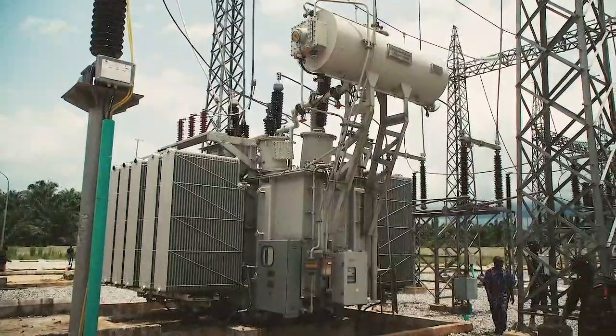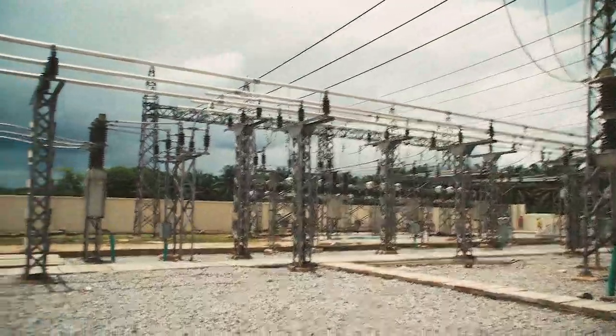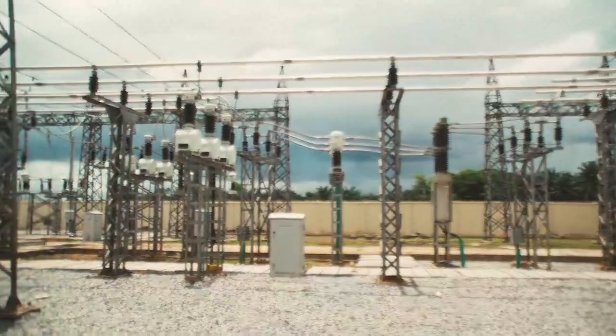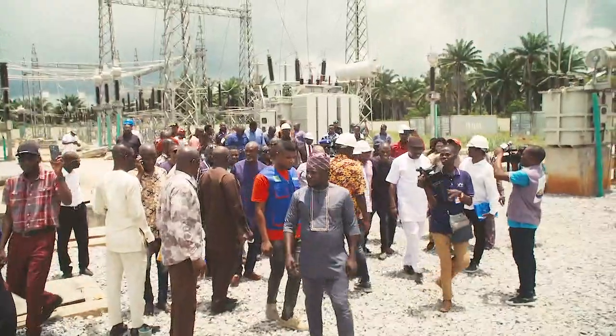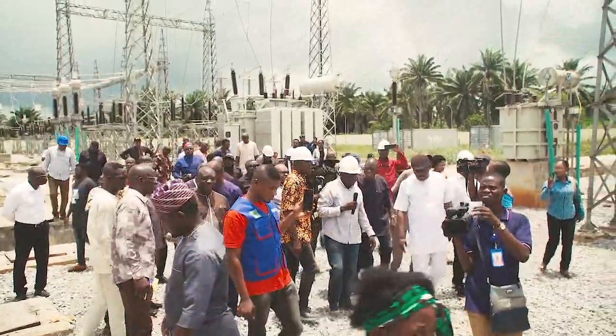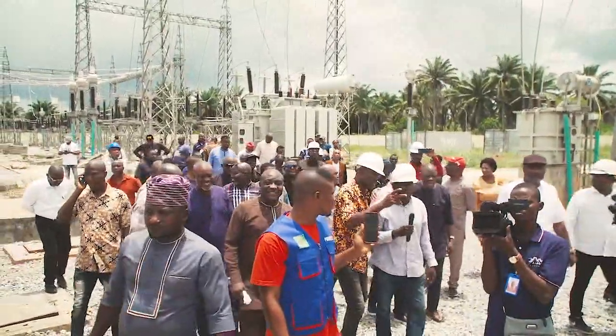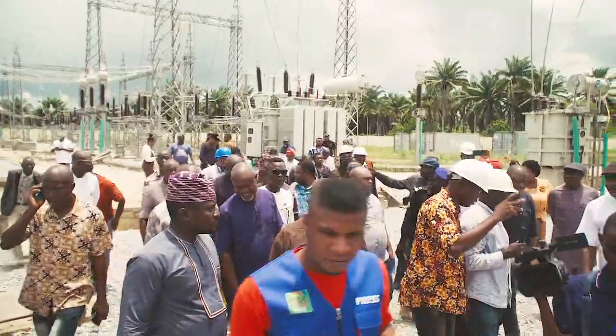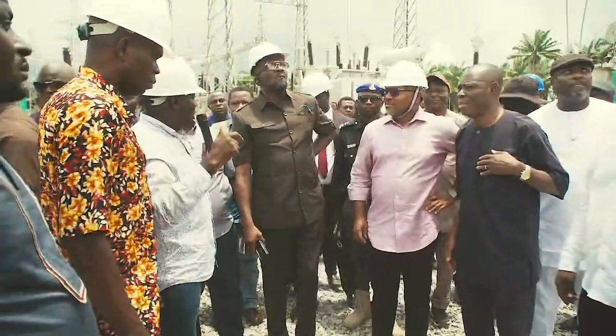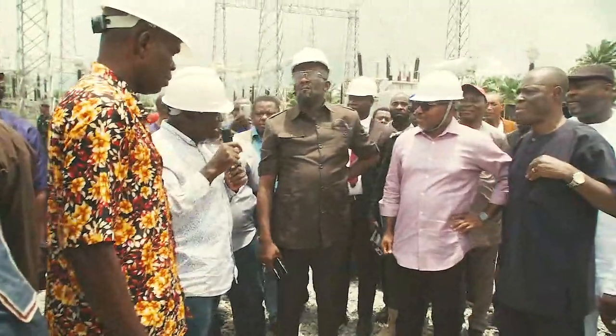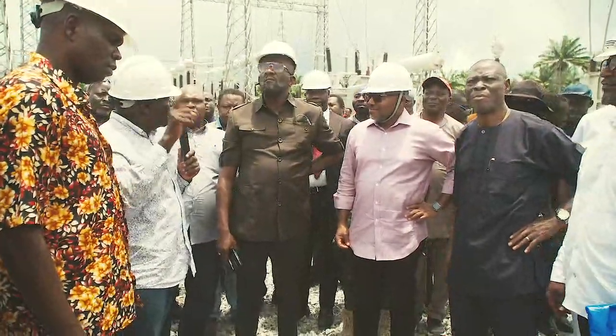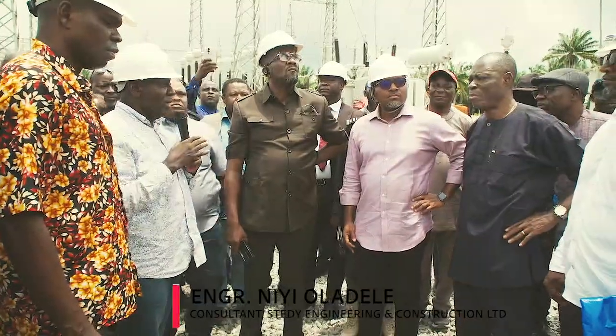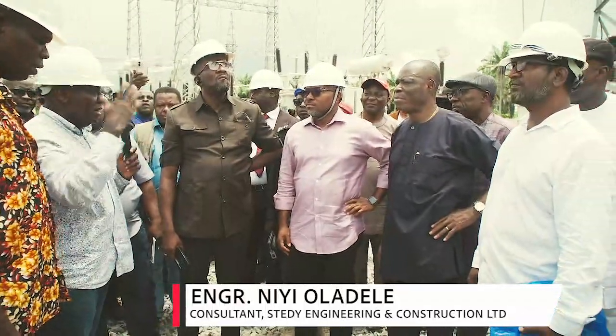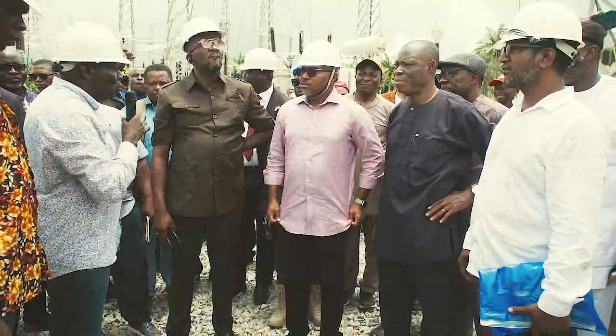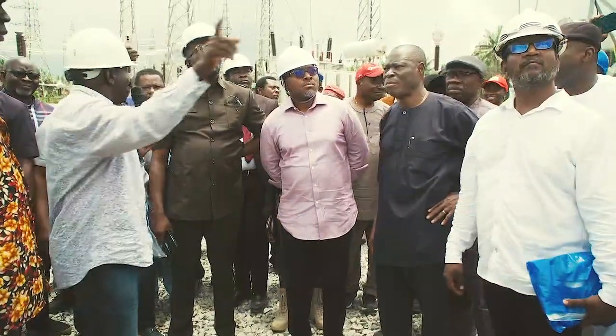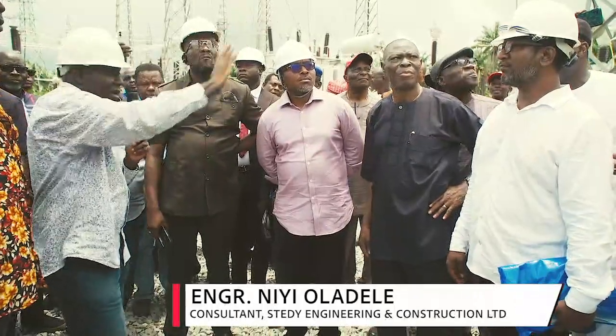Like I said initially, the equipment we are seeing on my right, they are all the secondary. The beauty of this power station is the installation incorporates a unique design. Usually, we normally have what we call main bus bar, reserve bus bar. Like I told you there, that we have bus 1, bus 2. But over here, we have a reserve bus bar apart from the main bus bar.